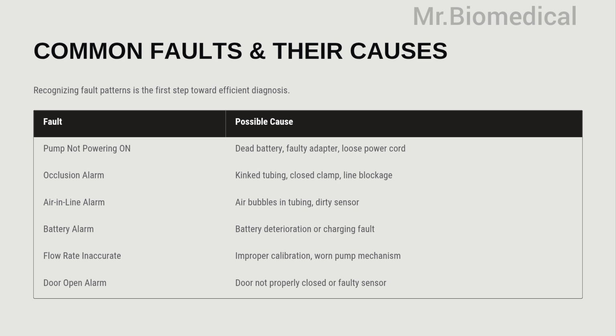And next is the air-in-line alarm. This occurs when air bubbles are present in the tubing or when the air sensor becomes dirty. Another common issue is the battery alarm, which usually indicates battery deterioration or charging problems. We may also observe flow rate inaccuracy, often caused by improper calibration or wear in the pumping mechanism. Finally, the door open alarm may occur when the pump door is not properly closed or if the sensor is faulty. Recognizing these fault patterns helps us quickly identify the root cause.